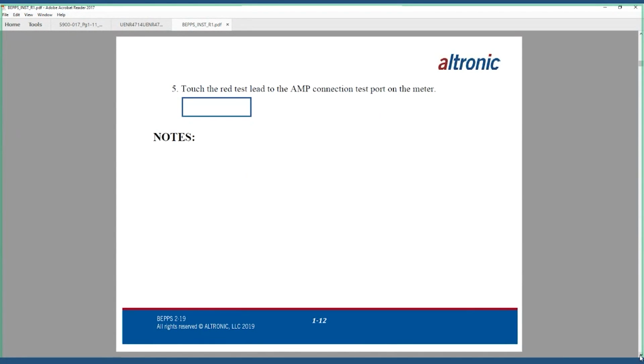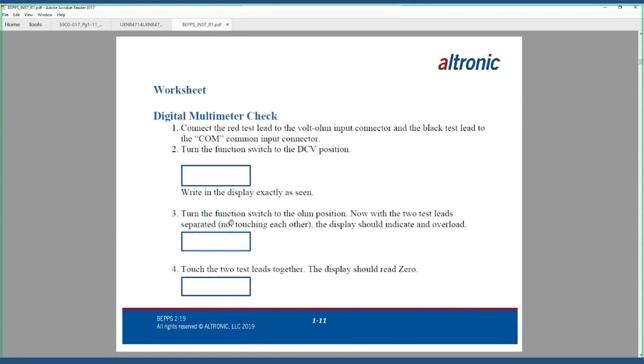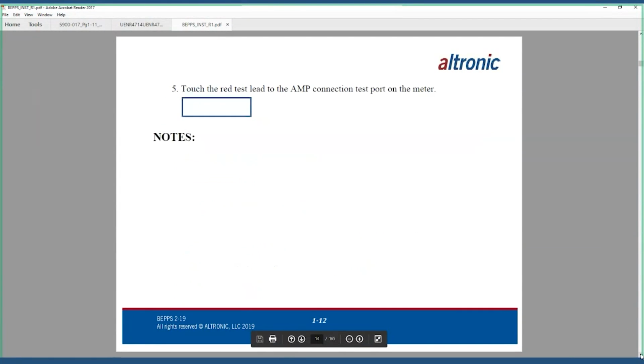Last test is to touch the red test lead to the amp connection test port on the meter and write down your reading. So if I back up a step, sorry, I'm having to look at one page at a time. So we have the function meter in the ohm position. What we're doing when we do this last test is we're checking the resistance to see if we have a good fuse in our meter.